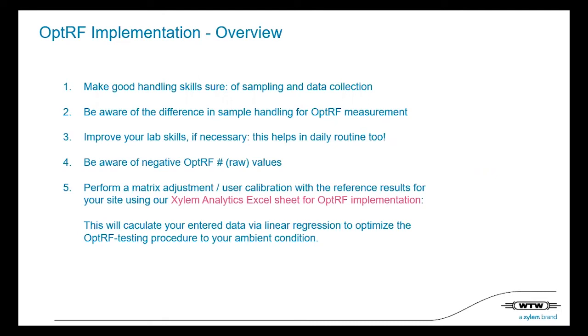I'll point that out in a second. There is a difference in handling of the samples, because the models are based on a constant stream in inline measurement, in situ measurement. Therefore, we do not filter any sample for the optical reagent-free measurement, which is different to routine analysis in some parts.